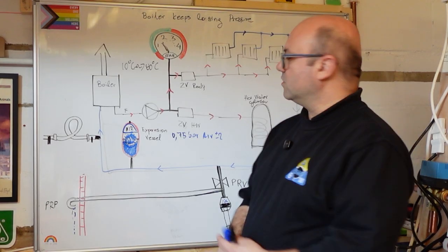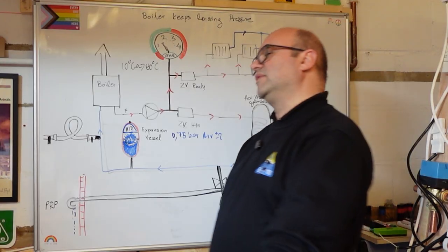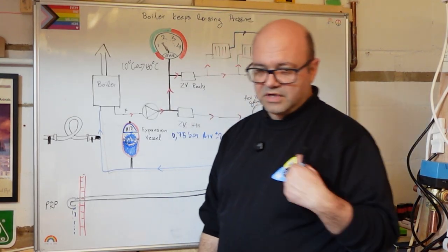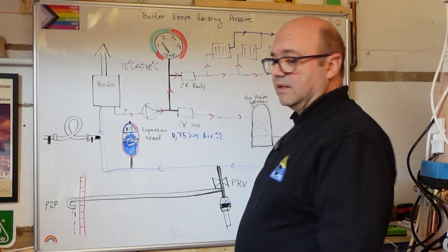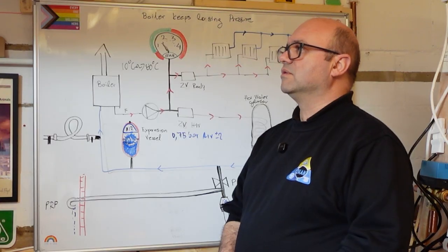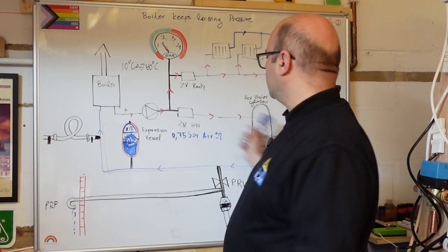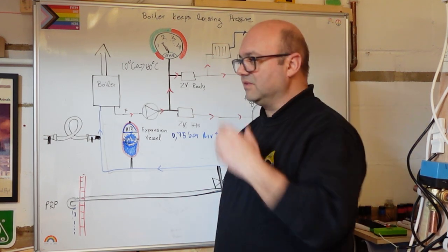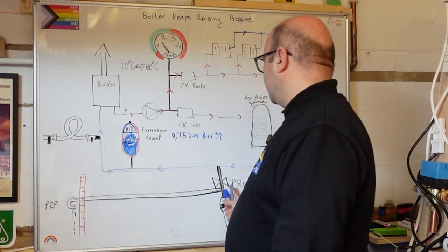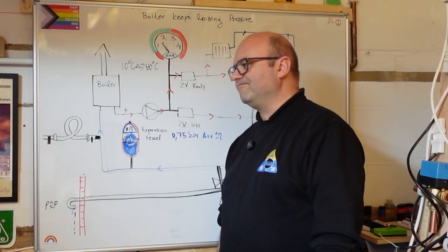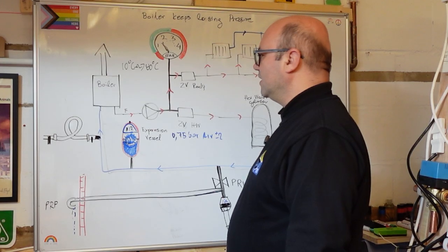What do we have to do in order to fix it? First of all, we have to recharge the expansion vessel, in case you're sure the expansion vessel is in good condition. Personally, I like to replace the expansion vessel, and the PRV as well. The reason we have to replace the PRV is because the PRV is always under dirty water. The circulation water inside the system is always slightly dirty, bringing debris, sludge, a lot of things. And as soon as this one opens, I'm afraid it's never gonna shut back. That's why we have to replace the PRV as well.